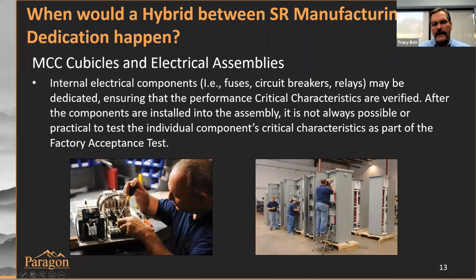Another area where we've got a hybrid approach, doing both dedication and manufacturing under our program, is motor control center cubicles and other electrical assemblies. We have a combination where components are going to be installed into an assembly, and in order to develop and verify the critical characteristics of the components going into that safety related assembly, the only real good way to verify those is to actually test and dedicate those items prior to installation.